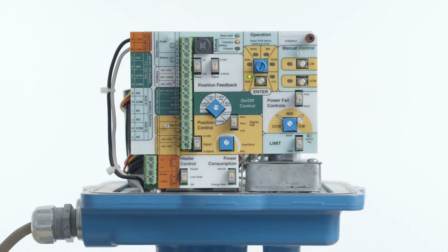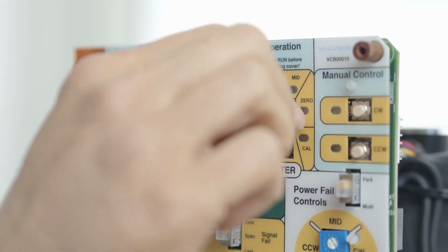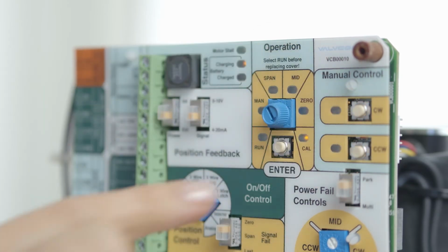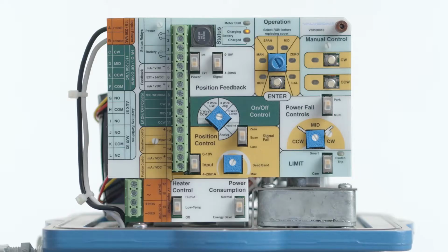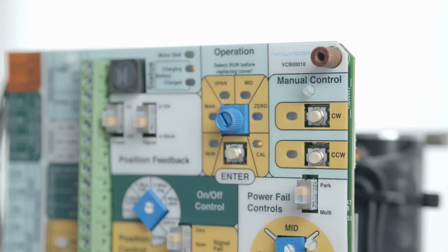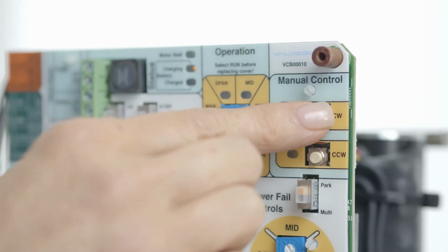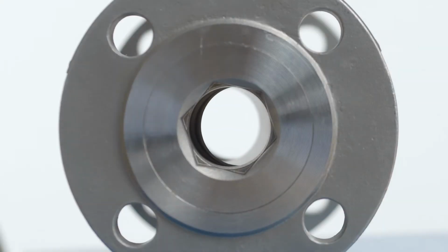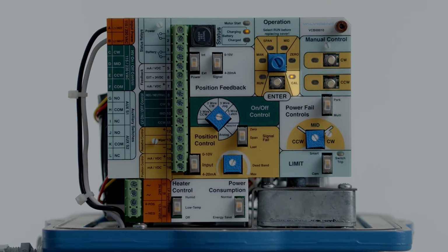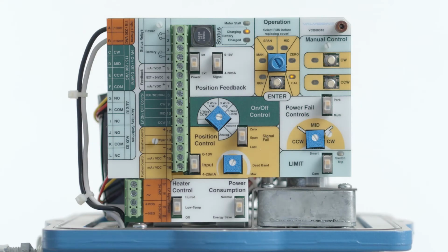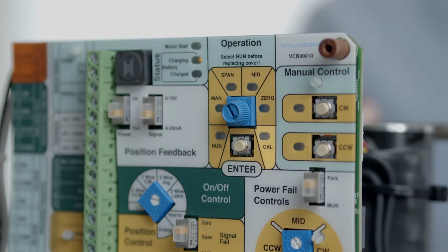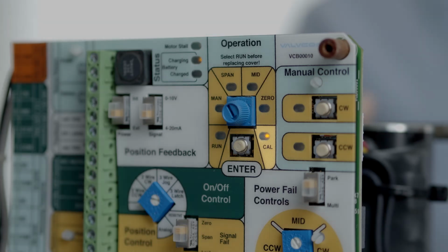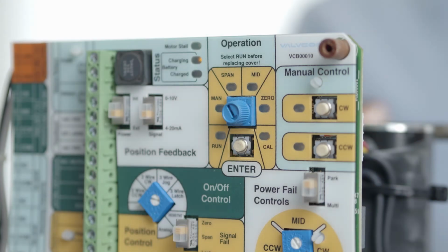To confirm proper potentiometer calibration, first turn the mode selector dial to Cal and then press Enter for 2 seconds. Using the CW push button, drive the actuator to the full clockwise position as viewed from above. For our demonstration, the valve we have is fully open at the full clockwise position. If the Cal LED remains on, no calibration is required. Proceed to the setting 0, mid, and span position section. If the Cal LED is flashing, potentiometer calibration is required. Again, at the full clockwise position as viewed from above the actuator.